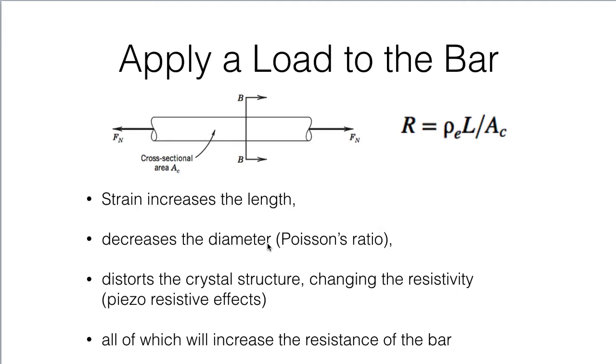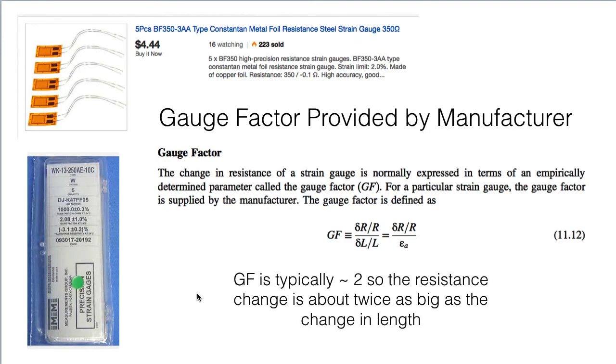The amount that the resistance changes relative to the amount that the length changes is called the gauge factor. And it's provided by the manufacturer. And it's a combination of all three of those effects that we saw. Increase in length, decrease in diameter, and the crystal structure distortion. It's usually right around a factor of two. So 2.08 plus or minus 1% for this particular collection of strain gauges. And that's the ratio between the resistance change and the strain change. So the change in resistance will be typically about twice as big as the change in length.